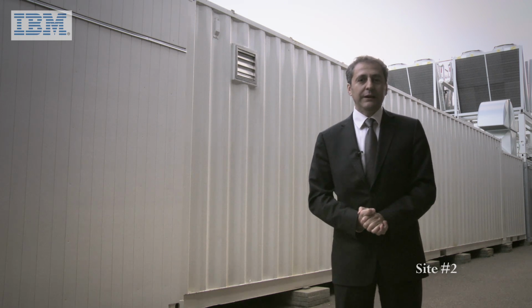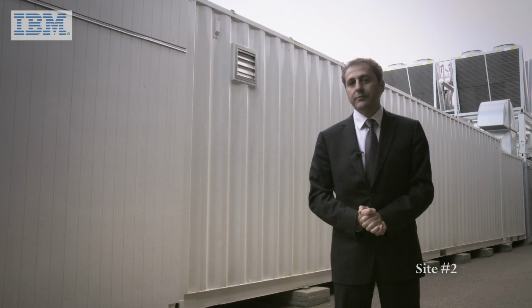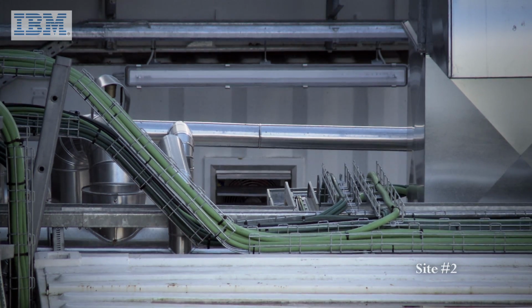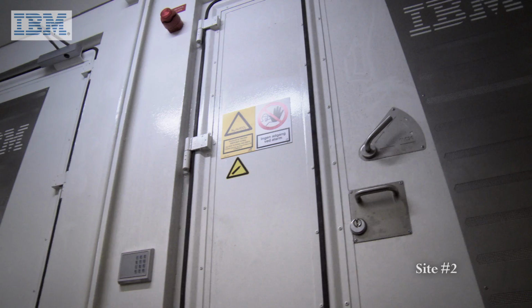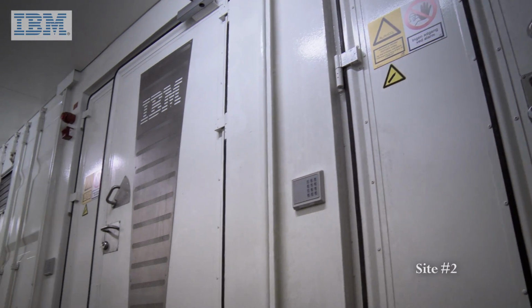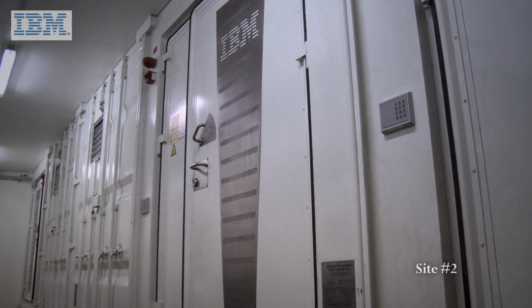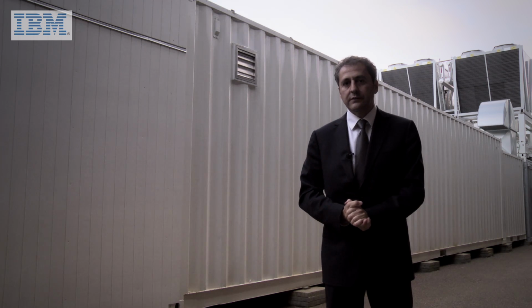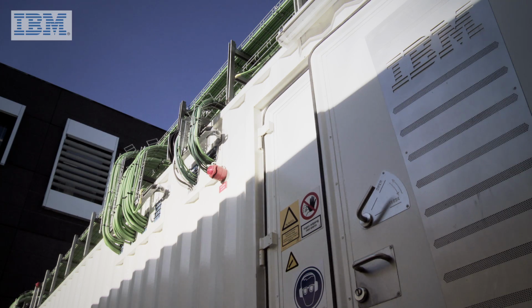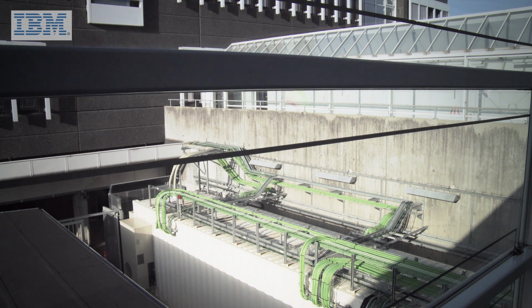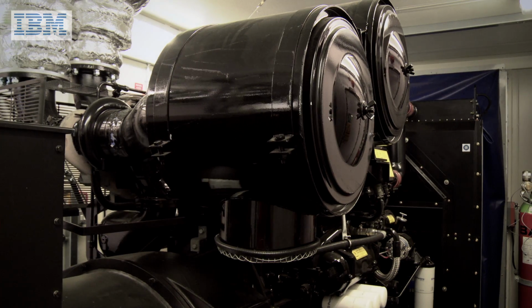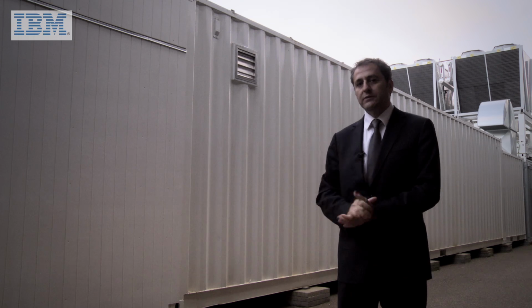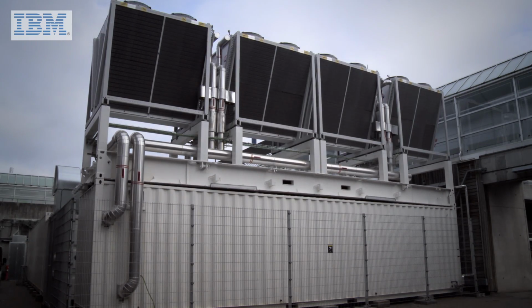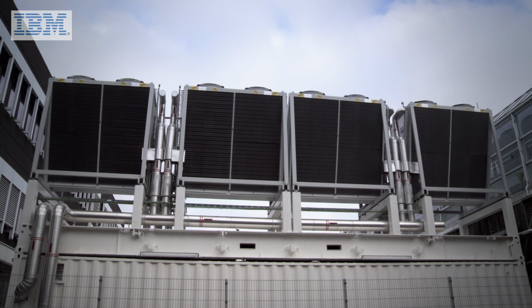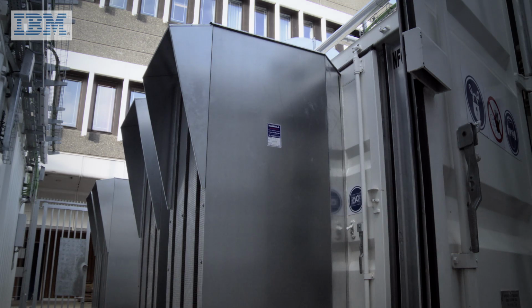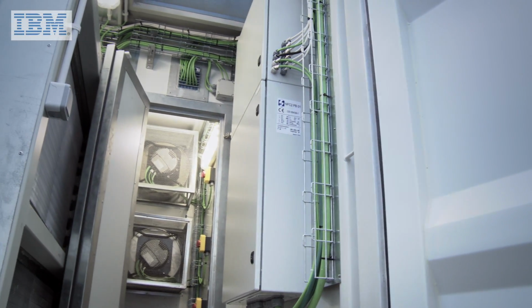So here we are at another IBM Modular Data Center site, also in Denmark. This is composed of 5 ISO 40 containers which provide hosting space for up to 70 racks with a total capacity of about 0.5 megawatt of IT power. All the operation is under a tier 3 configuration, including a dedicated power container and 2 fully redundant gensets. Also, as you may see behind me, there is a dedicated chiller container with the dry coolers on top. The IT containers are cooled by natural free cooling technology, also in a redundant configuration.